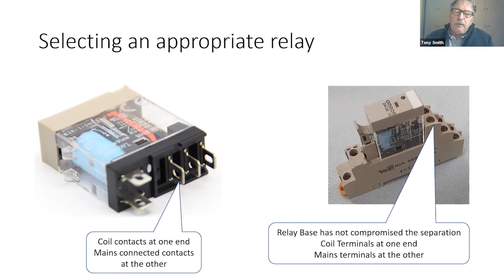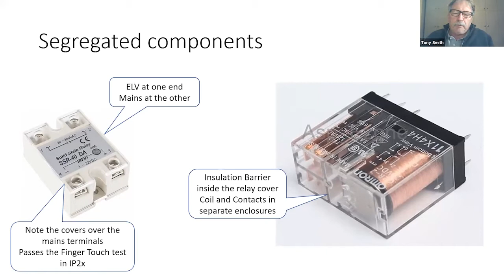A couple of cases here, you get these solid state relays. You can see this one on the left has physical covers over the 240 volt terminals and the 24 volt terminals. Again, that's really good design, but you need to select them very carefully. I was talking about relays having barriers in them - you can see this one on the right, in the plastic molding of the cover there's actually a physical barrier between the coil and the contacts. That's the sort of thing I'm talking about, just getting appropriate relays with segregation in them.